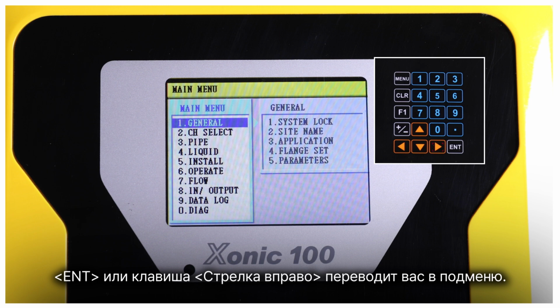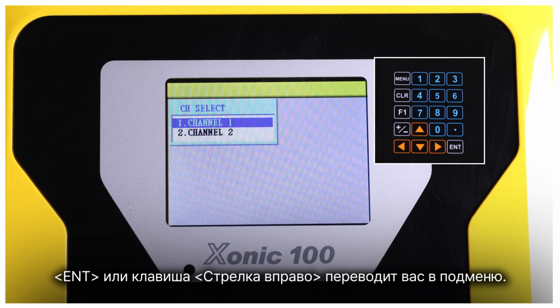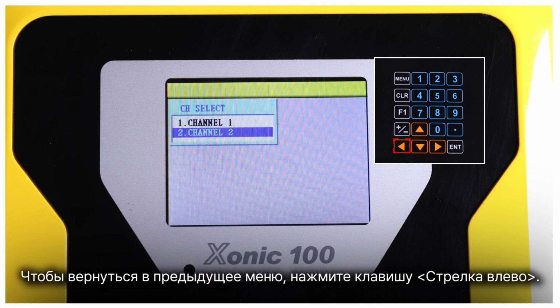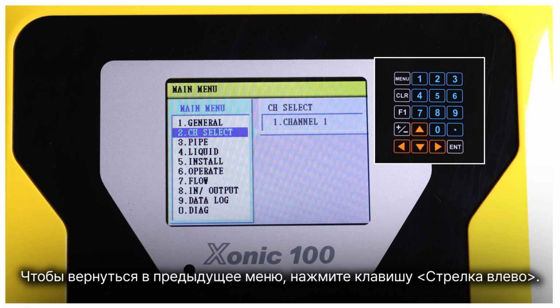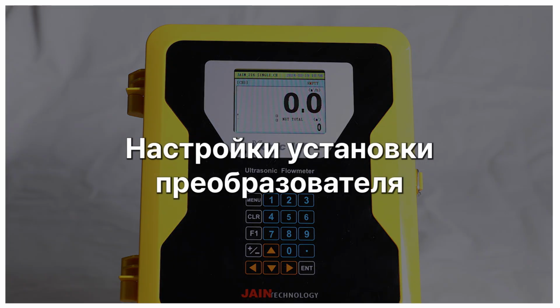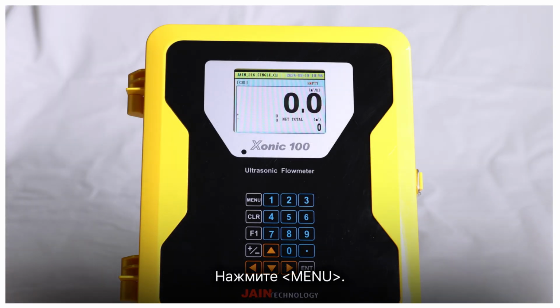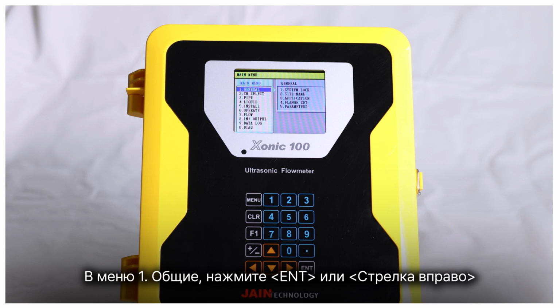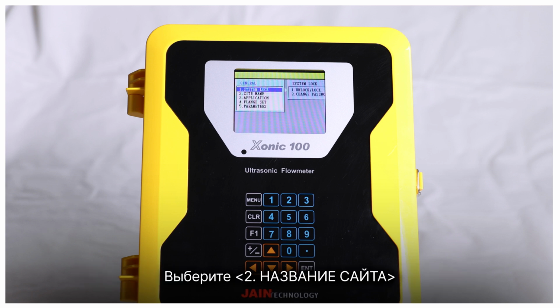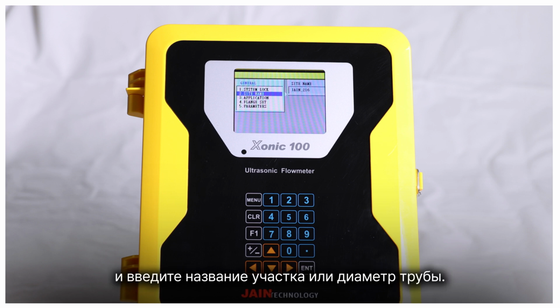Enter or the right arrow key leads you to the submenu. To return to the previous menu, press the left arrow key. Basic settings for transducer installation. Press Menu. On 1, General, press Enter or right arrow key to move to the submenu. Select 2, Site Name, and type the site name or pipe diameter.